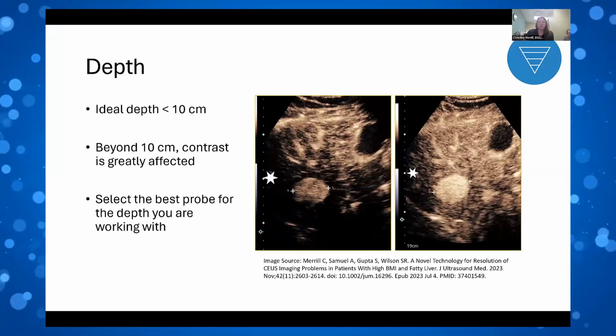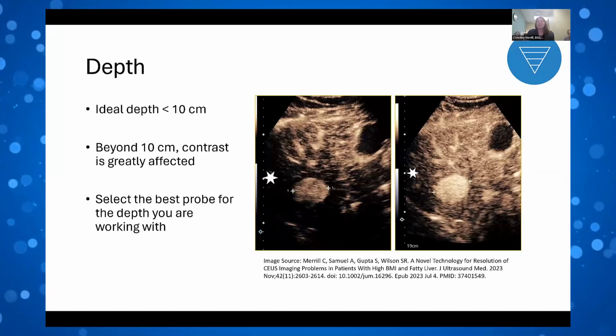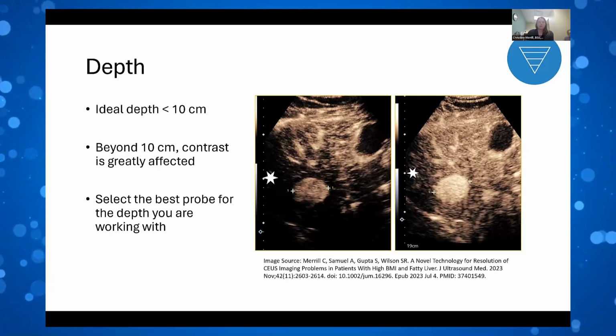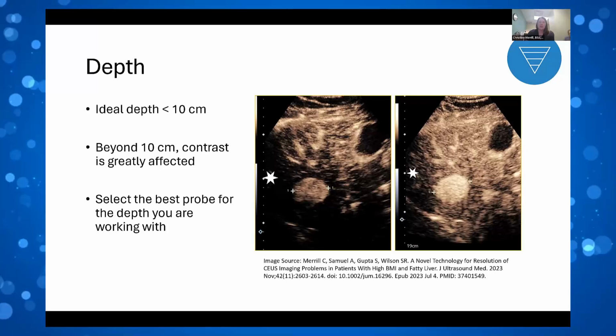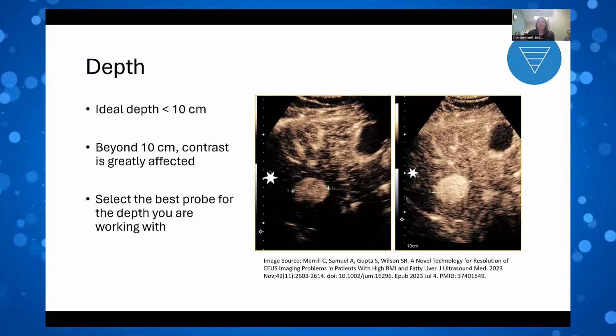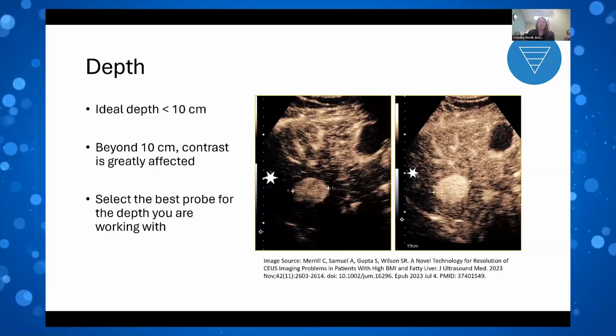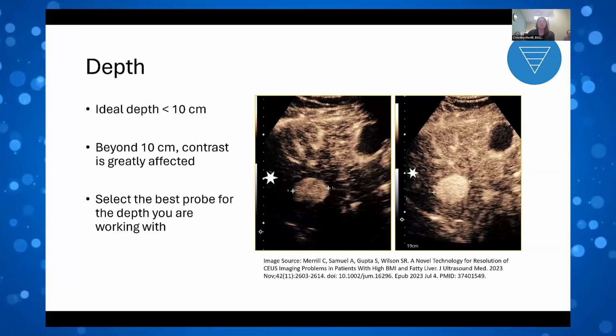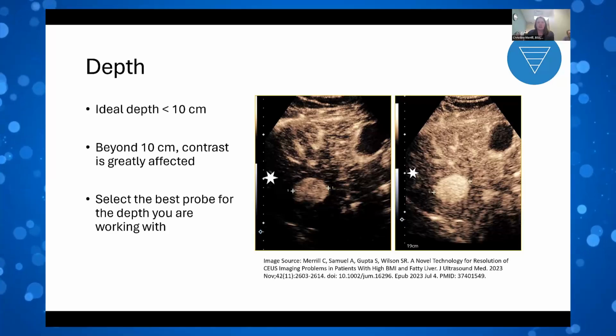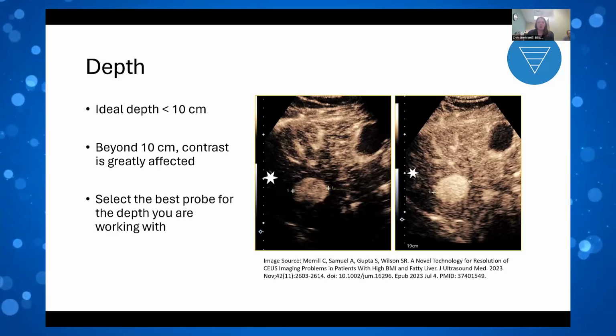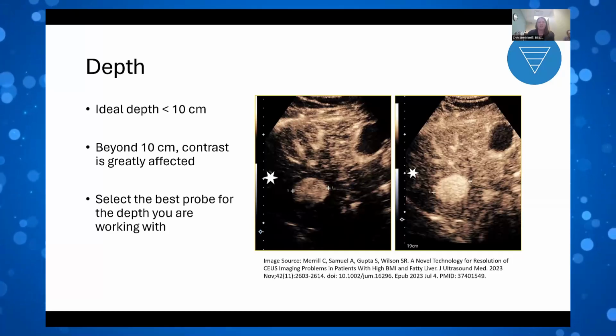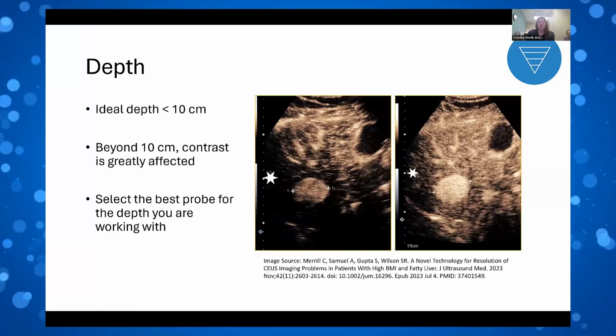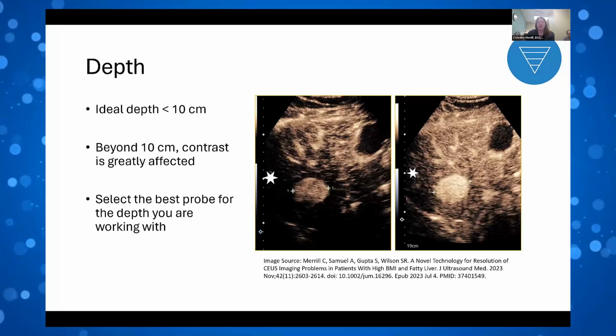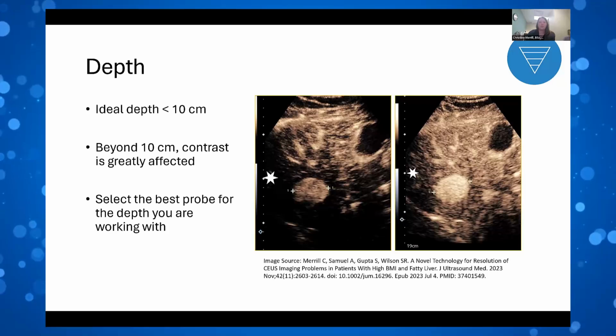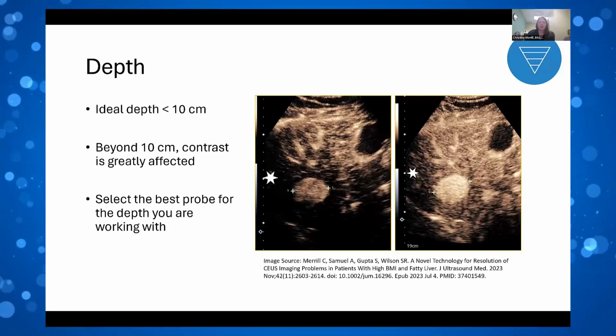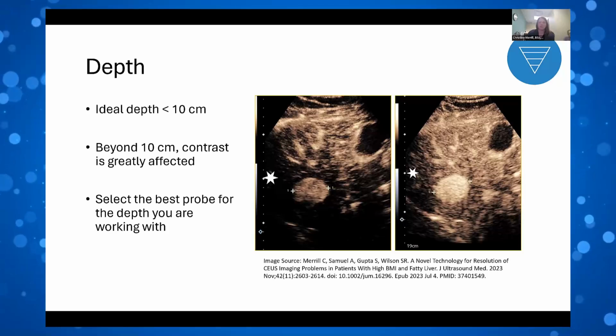So in an ideal world, we're going to want to set our depth to something that's less than 10 centimeters. And hopefully we've used our tricks with windowing and with patient positioning in order to obtain a window where this is possible. Beyond a 10 centimeter depth, the contrast is greatly affected. So you can see on the left-hand image there, the little white star along the margin just shows where that 10 centimeter mark is. And you can see that that lesion is deeper than the 10 centimeter mark, and how difficult that comparison is between the lesion and the liver, because we're really not getting even bubble distribution from the near field to the far field.